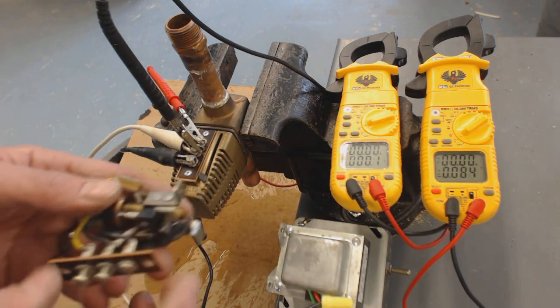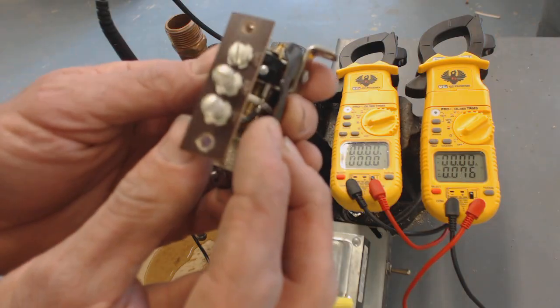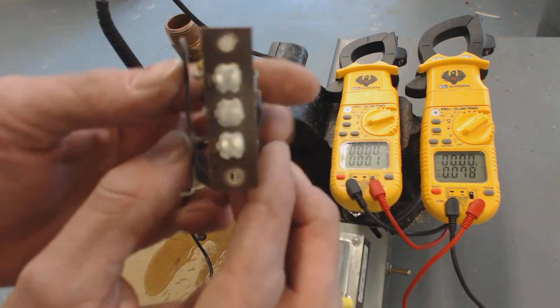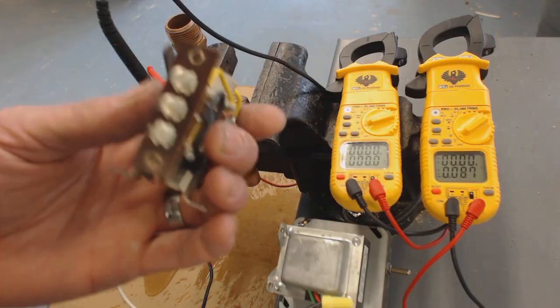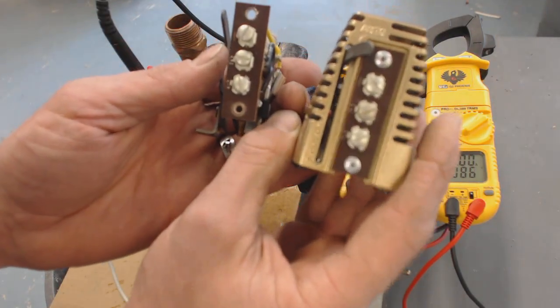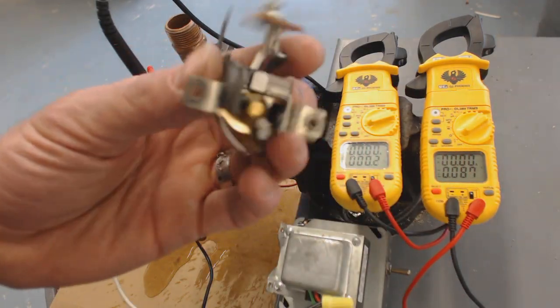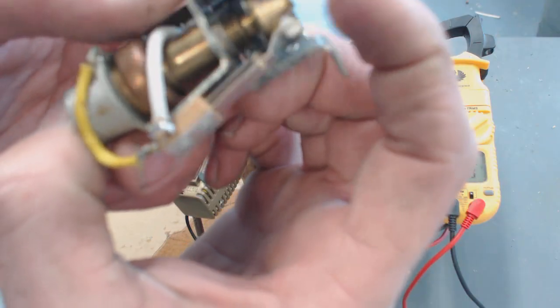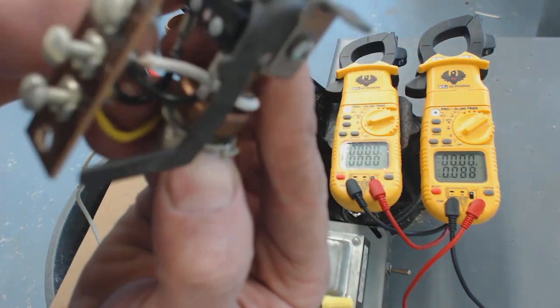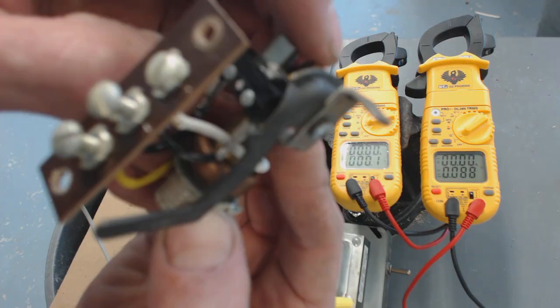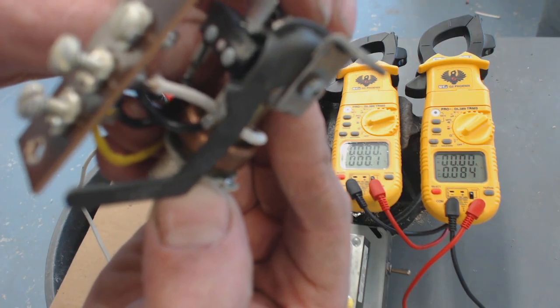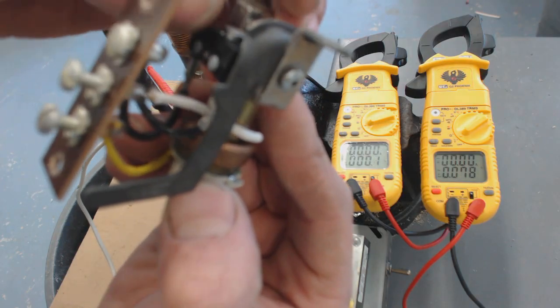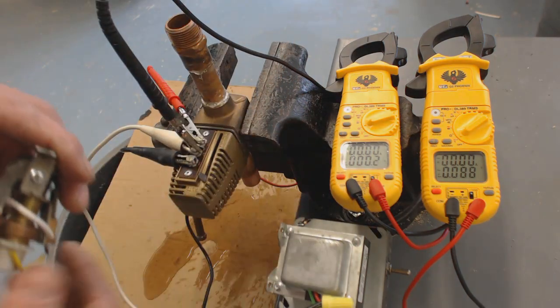And just so you know, on the inside of here, this is upside down right now from what this normally looks like. It looks like this. 1, 2, and 3. And inside here is that little plunger right here. I don't know if you can hear that clicking noise as it comes down. But it's actually pressing this little white micro switch in. What it's doing is pushing it and opening the valve.